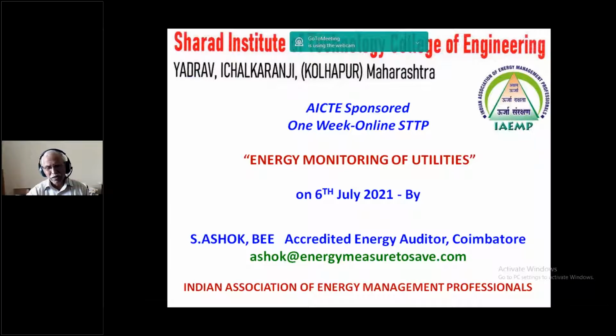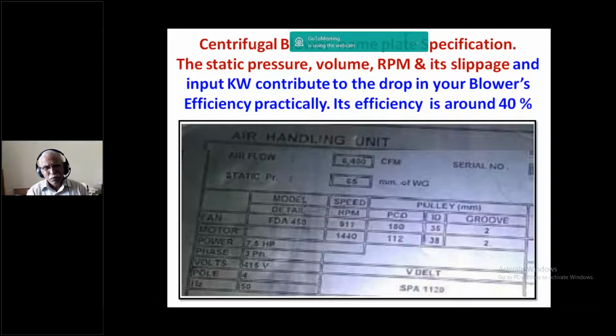in the utilities. And thanks to our Dr. Sanjay Khat, he suggested, let us concentrate. I am trying to concentrate on blowers and compressors where the Pascal monitoring is more important. This is what I just want to focus here. The Pascal monitoring. Pascal means it's Newton per meter squared. That is, normally we say before it was 1 bar and it came to 1 kg per cm squared, and then we talk in terms of Pascal. 1 bar, or 1 kg per cm squared, is almost 102 kilopascals. A slight difference is that around 14.2 to 14.5 psi between a bar and a kg.